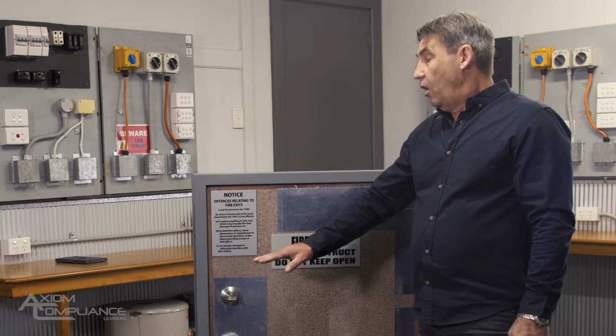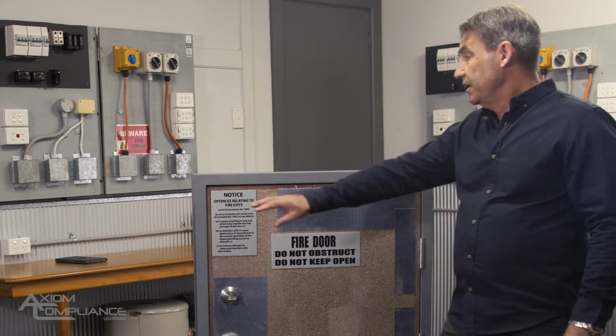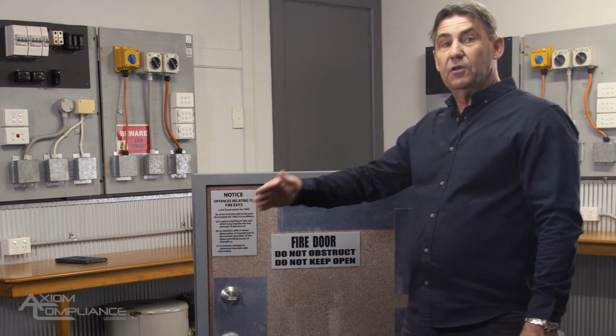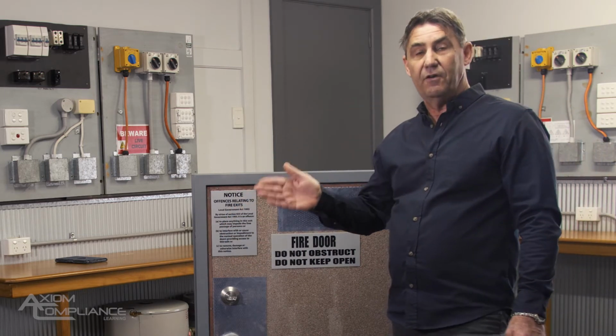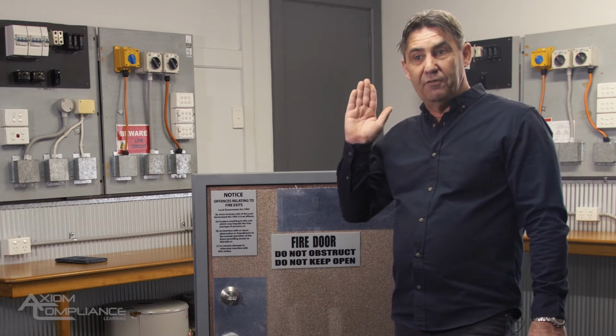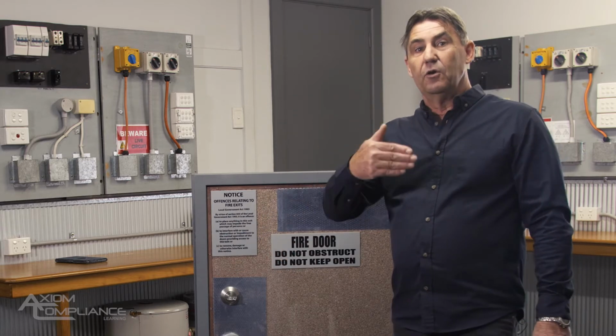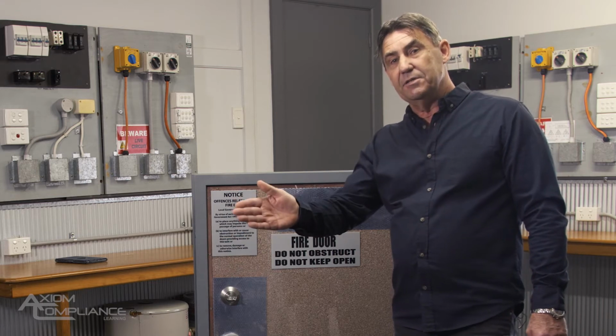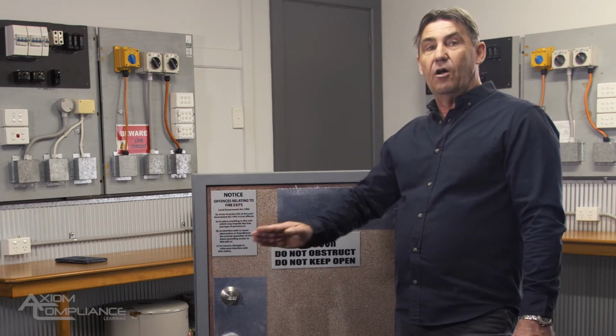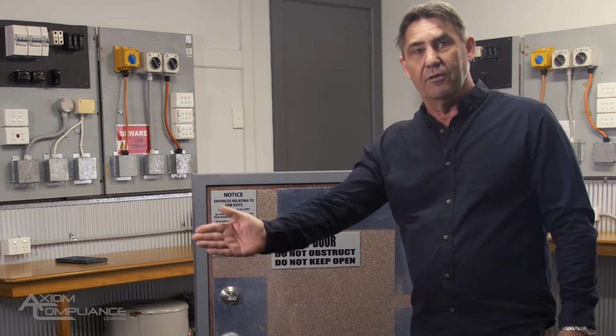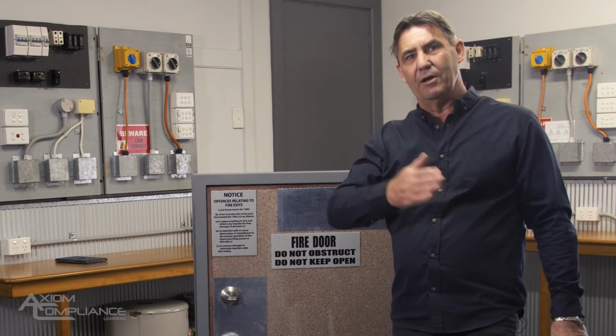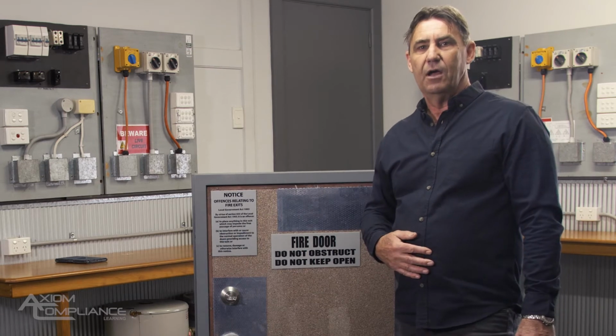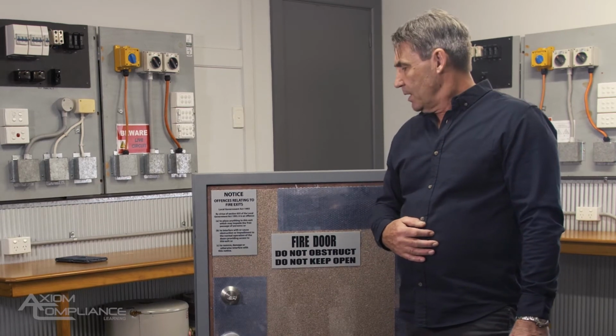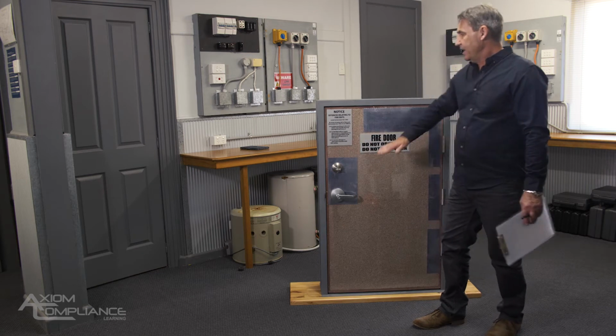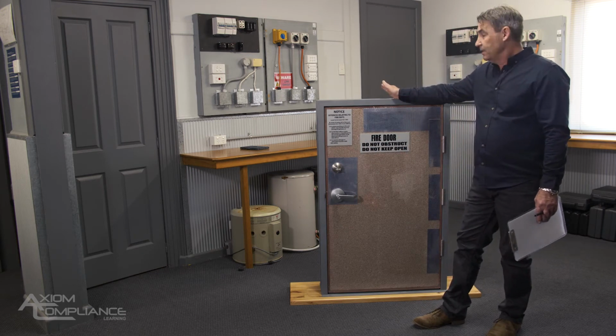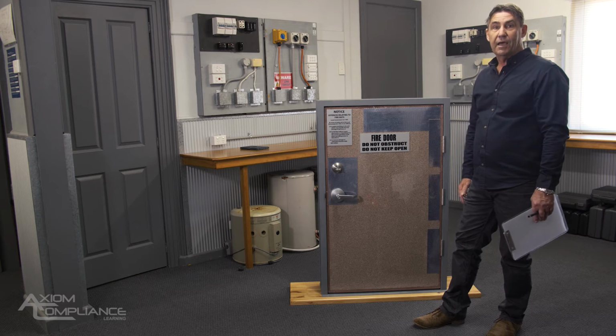So on the inside of a building, this signage is only required if you're egressing into an isolated fire stairwell. So an actual fire escape system, every door within the building that opens into that fire escape system must have this signage on the egress point. So not on the off side of the building, but on the entry side of the fire stairs. Okay, so the signage this side looks okay. We'll look at the other side of the door in a second, but all that signage looks okay from this point.